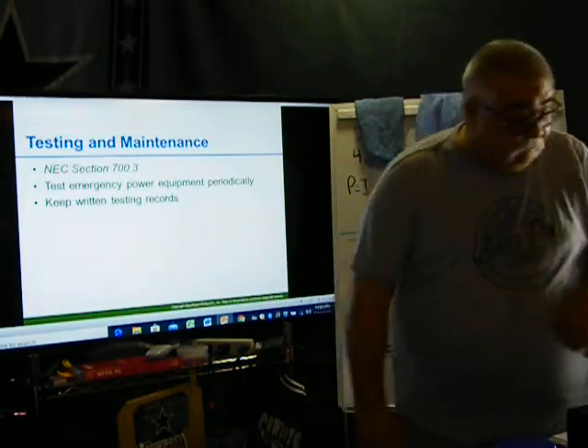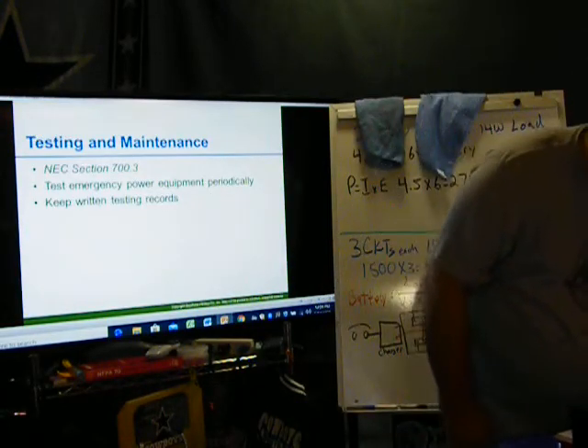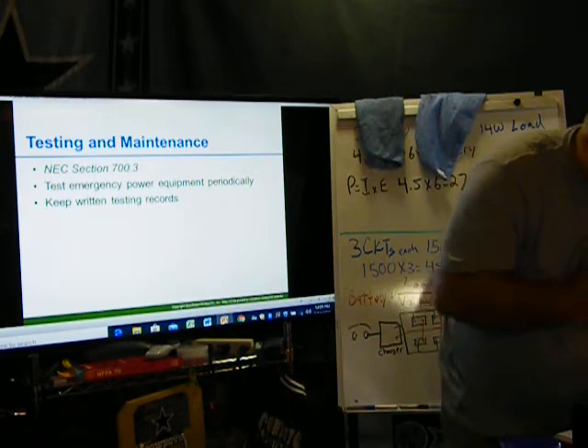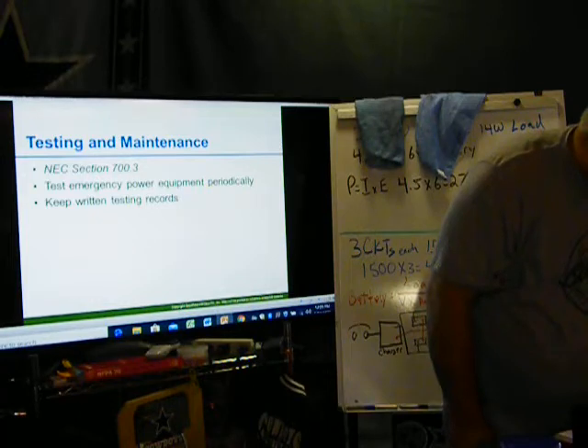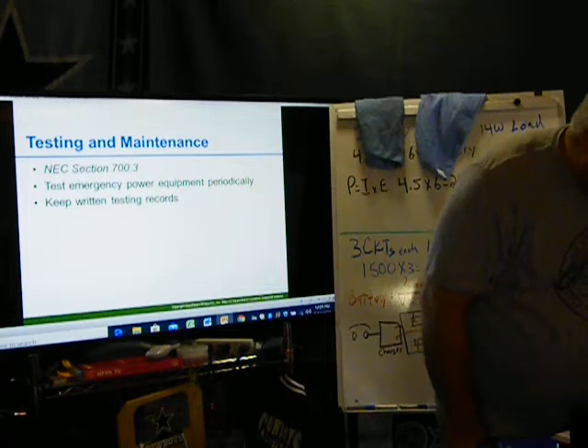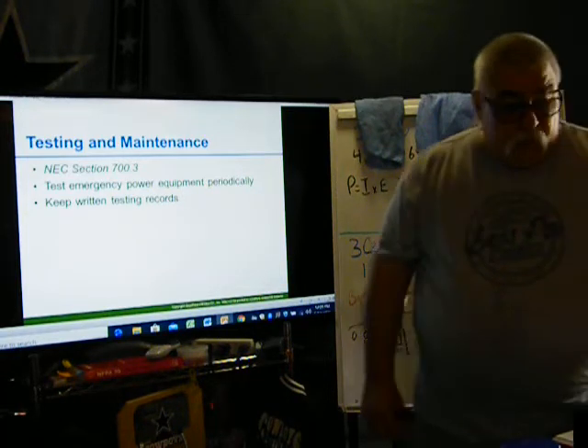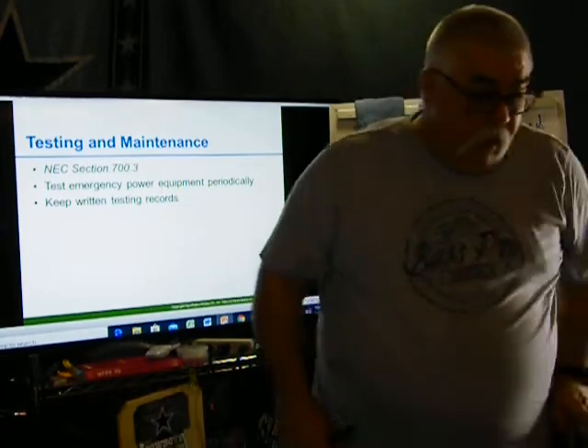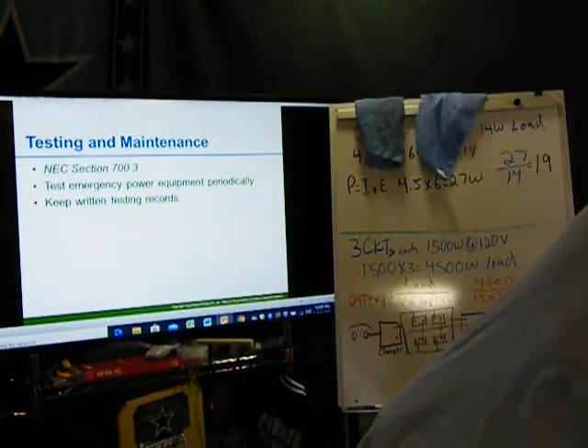Testing and maintenance. 700.3 requires that equipment used as emergency power equipment be tested periodically. The authority having jurisdiction shall conduct or witness the system testing and decide on a set schedule for testing and periodic maintenance. A written record must be kept. Okay, so that's why I was reading off the instruction sheet. Okay, so this is where the instructions come in.